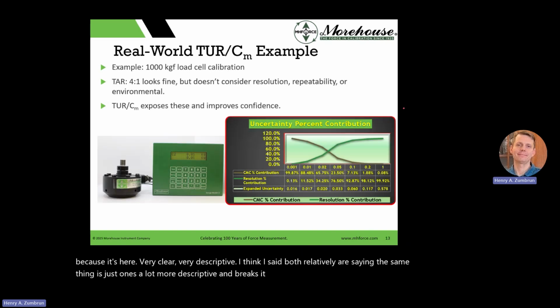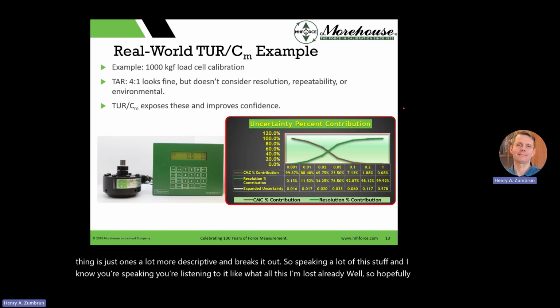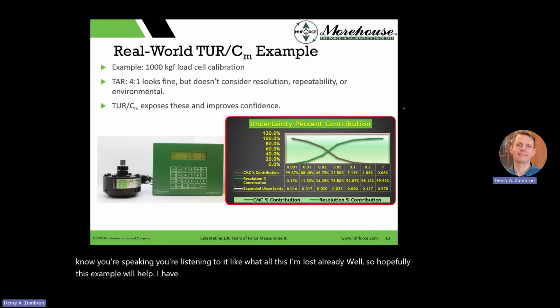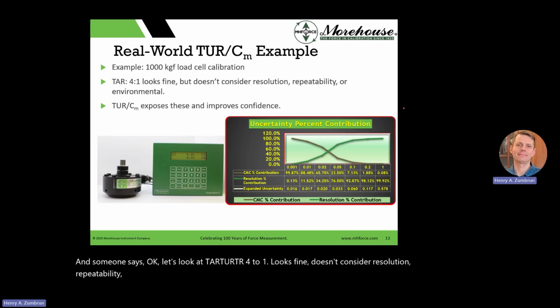So, speaking a lot of this stuff, and I know you're listening to it, like, what else, I'm lost already. Well, hopefully this example will help. I have a 1,000 kgf load cell. And someone says, okay, let's look at TAR, TUR. TAR 4:1 looks fine, but it doesn't consider resolution, repeatability, or environmental effects. TUR, the calibration measurement capability index, exposes these and improves confidence.